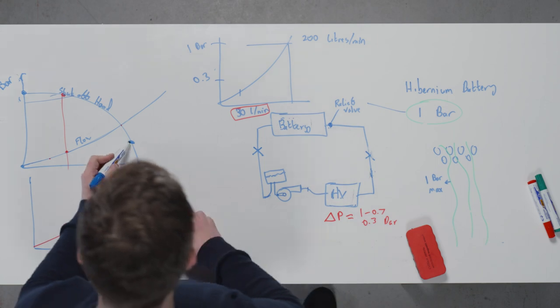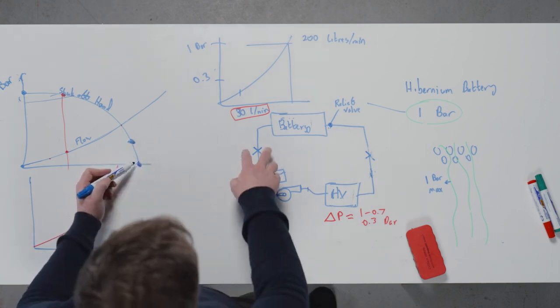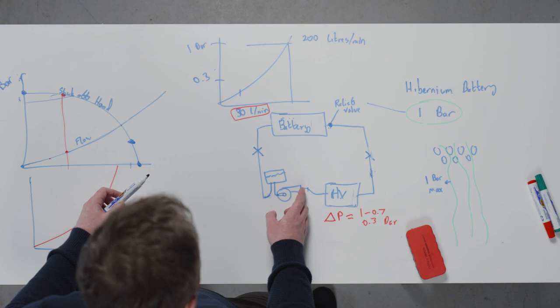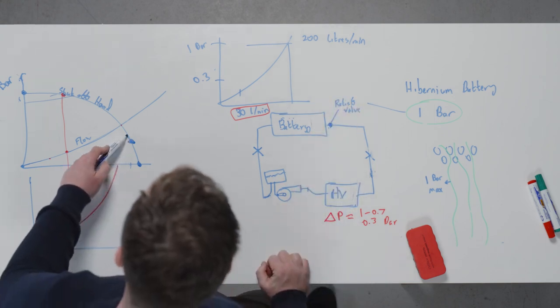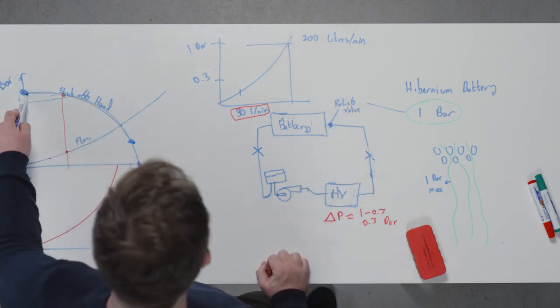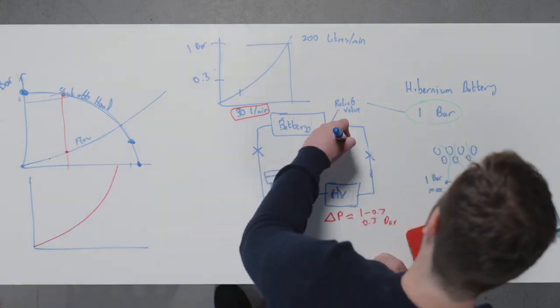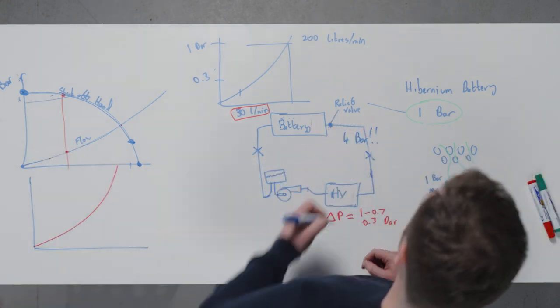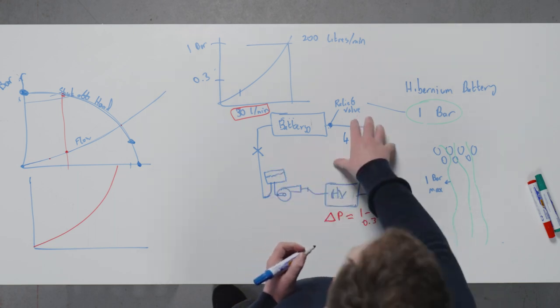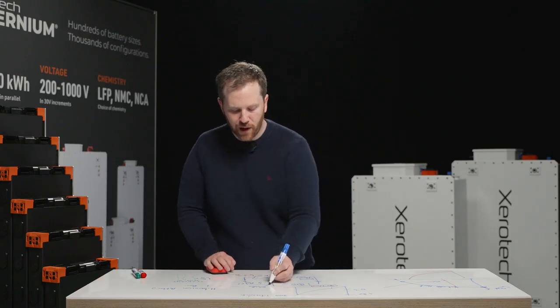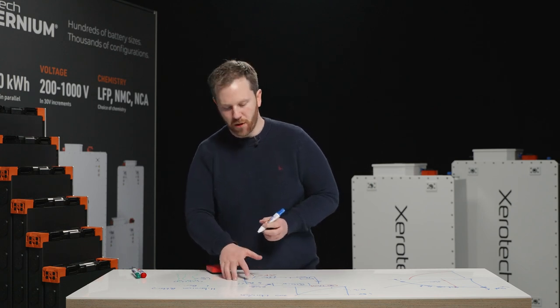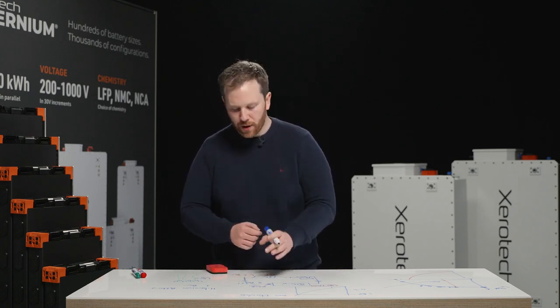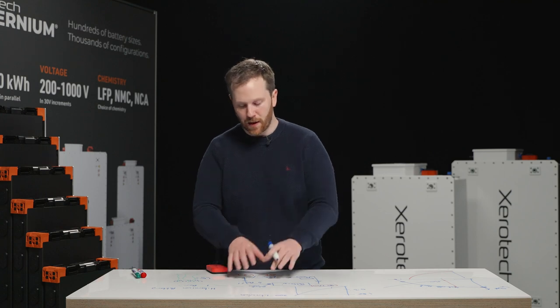What's going to happen here is that no flow can develop. It's a fully constricted pipe. The flow will be stopped, the pump will be at maximum. It's going to shoot up to the shutoff head of the pump. So the system here could be up at 4 bar of pressure or whatever the shutoff head of your pump is. That's why a pressure relief valve is so important, and that's why it's very important to be careful with your valve design. The most common failures that we see in a mistake in integration is with multi-packs, especially with flow balancing valves. And we're going to talk about that next on some of the key watchouts.